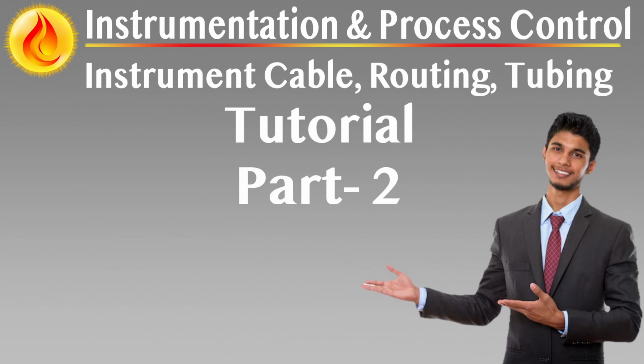Pneumatic tubing must be designed and installed to maintain signal pressure integrity, resist mechanical damage, and facilitate future maintenance or expansion. Single tubing runs connect field instruments, such as pressure controllers or pneumatic transmitters, to junction boxes. From there, multi-core pneumatic tubing routes signals back to the main distribution frame, MDF, in either the central control room, CCR, or a field auxiliary room, FAR.